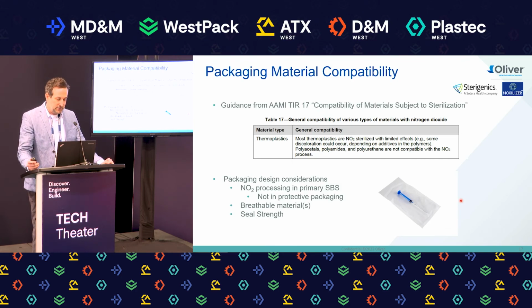So some of the design considerations: you want to process in the packaging, the primary sterile barrier system. Alan touched on it. You don't want to be in a carton, in a shipper. It's not compatible with paper-based, cellulose-based products. So you're doing it right in the sterile barrier packaging pouch or tray system, directly in there, and then putting into your protective packaging afterwards. Also, it's not on here, but you do want breathable materials, but you want to stay away from medical paper. For the same reason as cartons and shippers, you want to stay away from medical paper. So we highly recommend Tyvek for that.